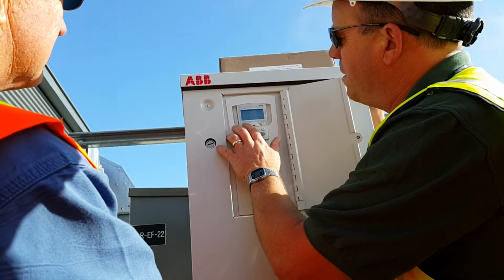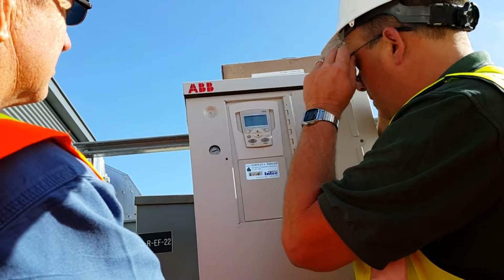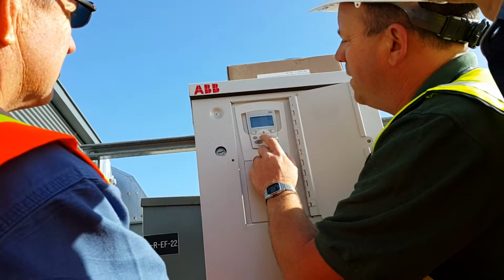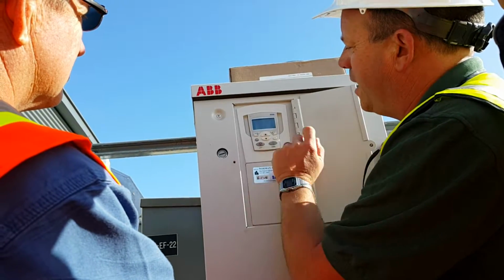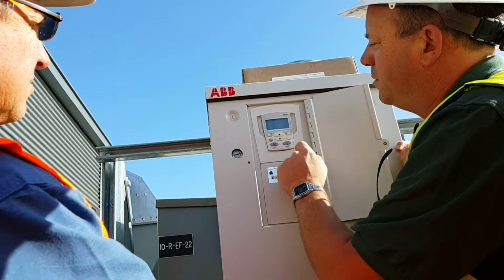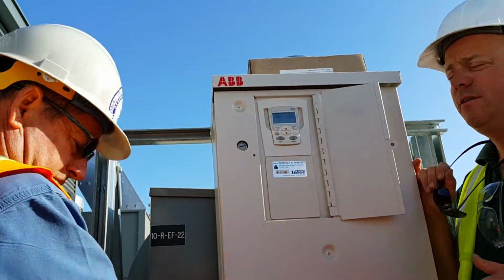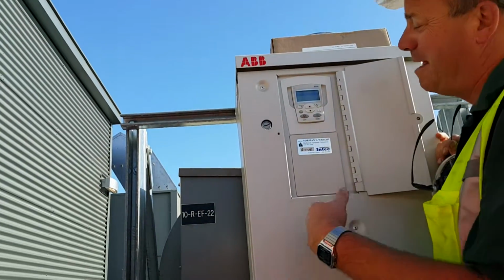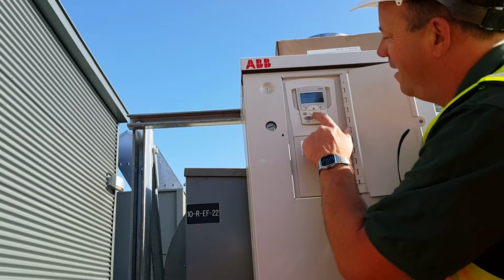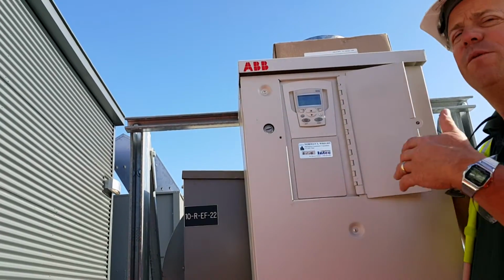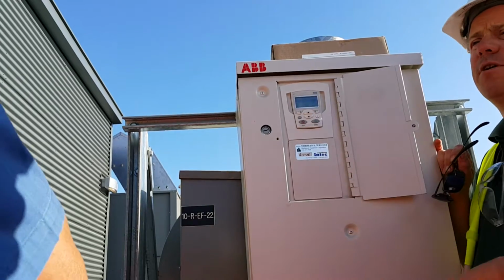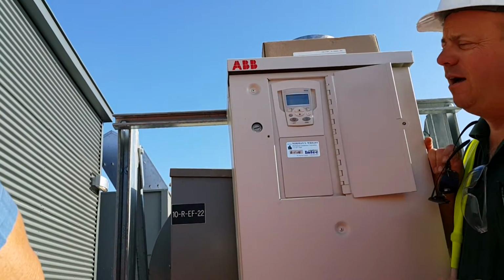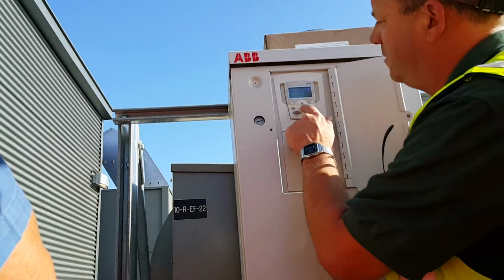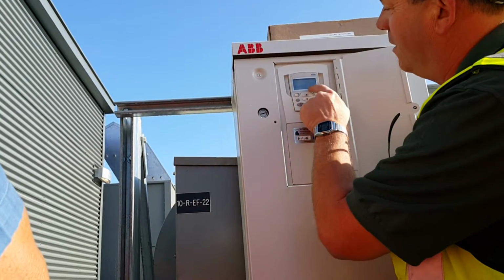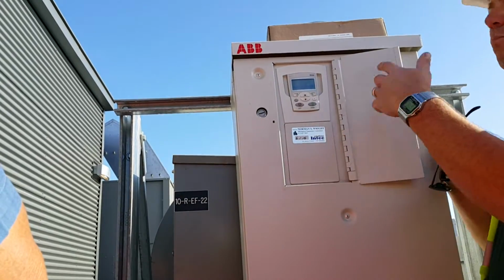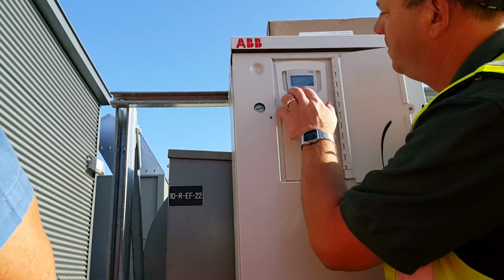We'll go all the way back to the main menu or the main display. We'll hit menu. Some things that are really nice to look at is change parameters. It'll show all the parameters that we changed. I particularly changed in this case. Somebody came behind me. All the things that I changed from the default, so things to set it up for your accel, your decel, your motor data, your control inputs, those types of things. And we can look at any of those, like maximum current, 9.7 amps. The default was probably much higher. Change it to the FLA of the motor, things like that.